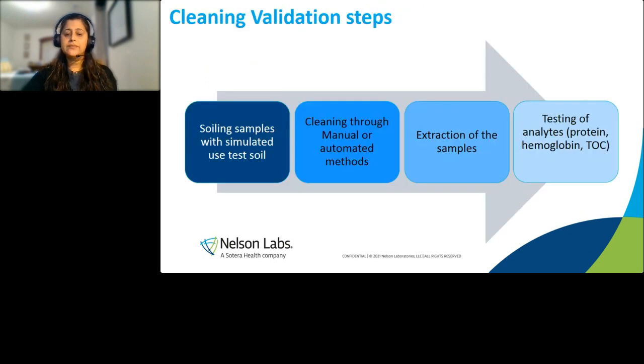Now, for cleaning validation steps, it's basic, simple. It's only 4 steps. We soil the devices with simulated use test soils. Here, we're just guessing what the test soils would be, or we work with the manufacturer to see how the device is used, the intended purpose of the product, and try to come up with a test soil that mimics the product. After that, we're cleaning it through manual or automated methods, depending on the IFU that's provided by the manufacturer. We extract those sites that we are cleaning, and then we test for the analytes.